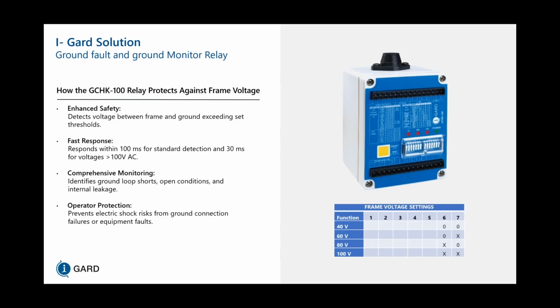What is the voltage for standard detection of 100 milliseconds? So if the voltage is less than 100 volts AC, then it responds within 100 milliseconds. But if it's greater than 100 volts AC, then it's at 30 milliseconds because it's easier to detect. How do we get to the schematic of the relay? How is it installed? You can view our manuals on our webpage, and that would give you the information on how this unit is connected. We can also provide you with the manual and brochures alongside the presentation slides that will be sent to you.